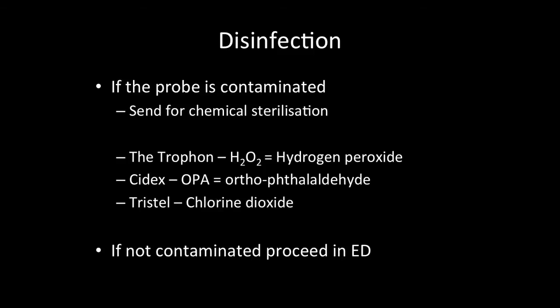If you get any patient bodily fluids onto the transducer or the cord, it's really important that it's decontaminated properly, and that involves high-level chemical sterilization. There are a number of options for that. One is the Trophon, which uses hydrogen peroxide. Another is Cidex, which is orthophthalaldehyde. And the third is Tristel, which uses chlorine dioxide.